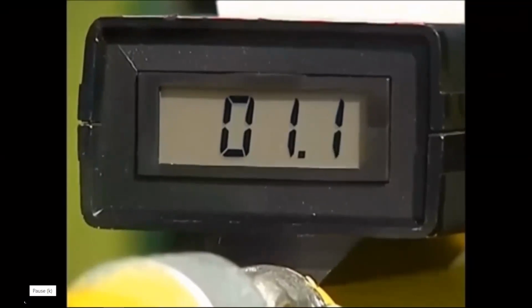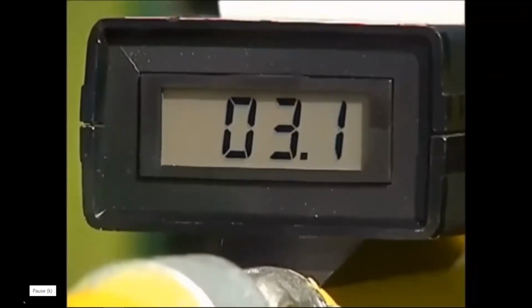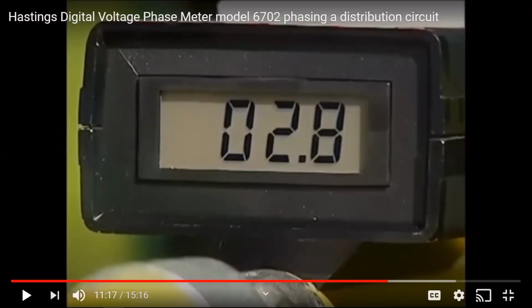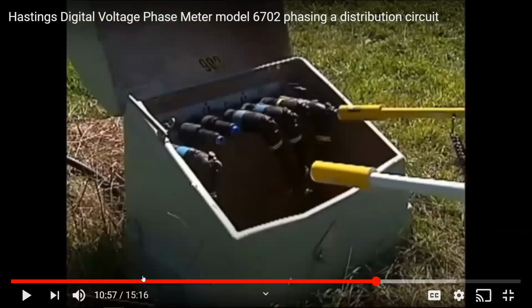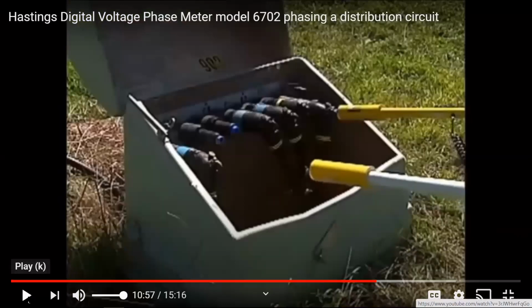It's obviously a punctured cable. It's dropping back off again. Okay, see what happened right there? Started high, went down, and went back to high. Okay, I'm going to re-show that one again. Thank God that's a punctured cable, right?